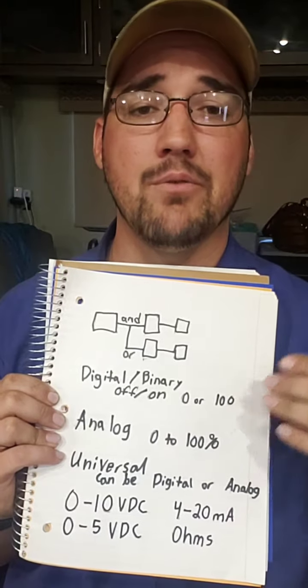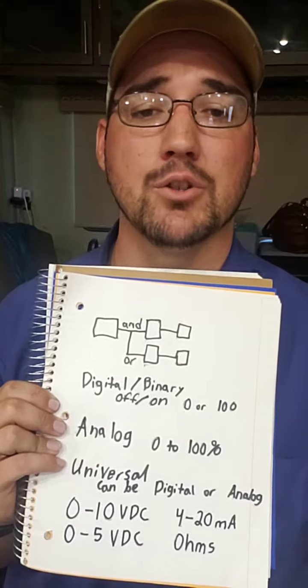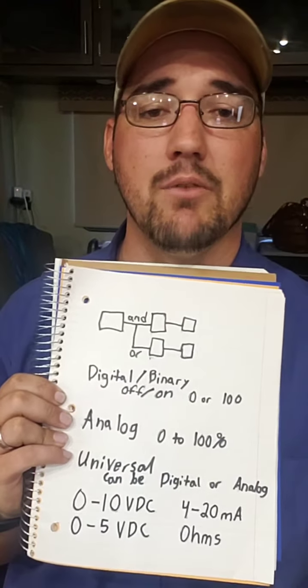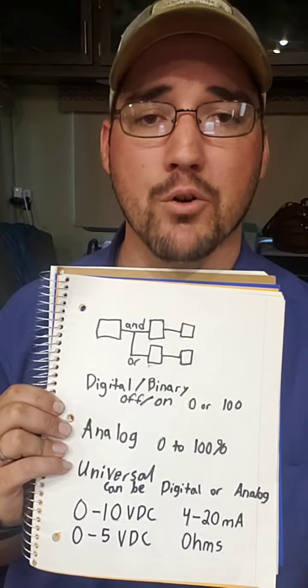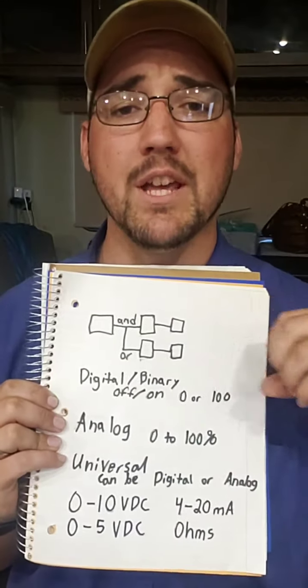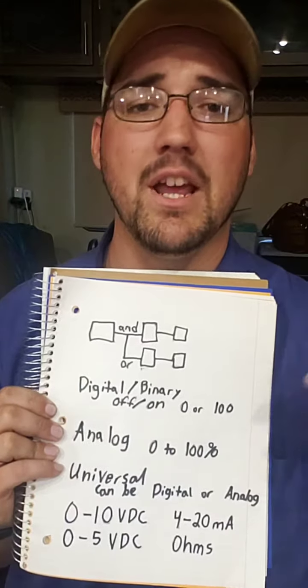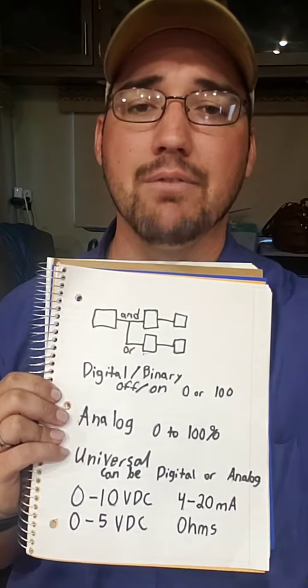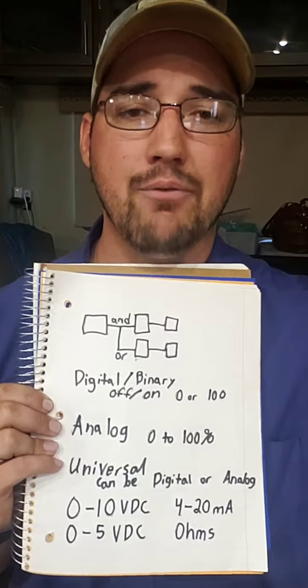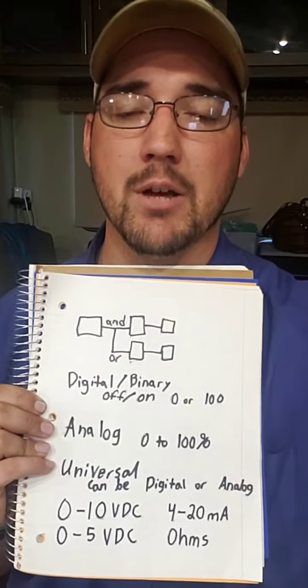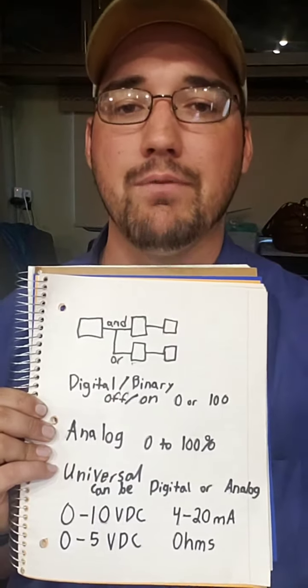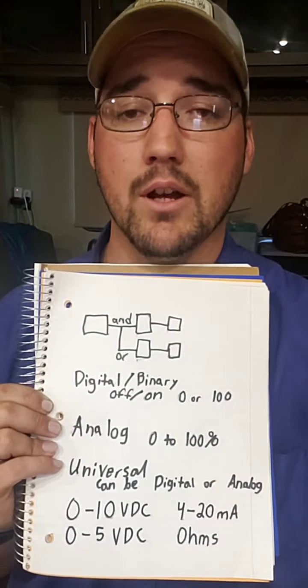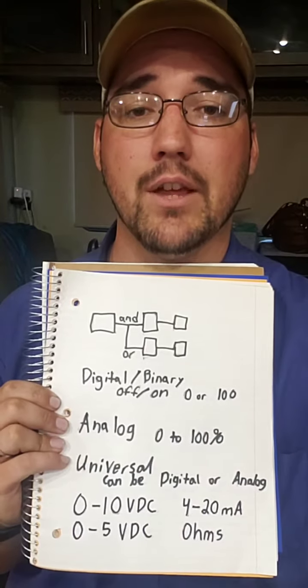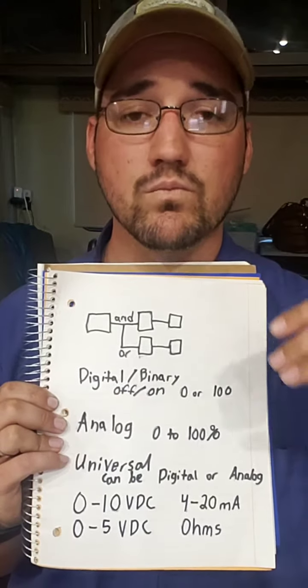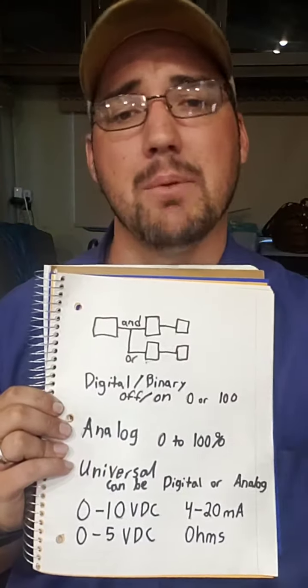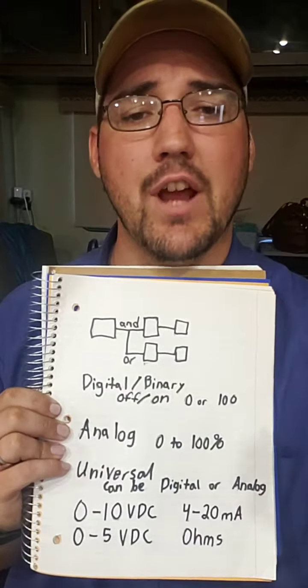The same thing applies if you do a lot more heavy commercial work: a VFD, a variable frequency drive, controlling a motor of some kind. We give a voltage signal or a milliamp signal to that VFD, telling it, okay, if you're at 5 volts DC input coming into that VFD, I want to run at 50%, or be at 30 hertz as far as that VFD is concerned. That's a whole other topic, but anyway, that is your analog output.